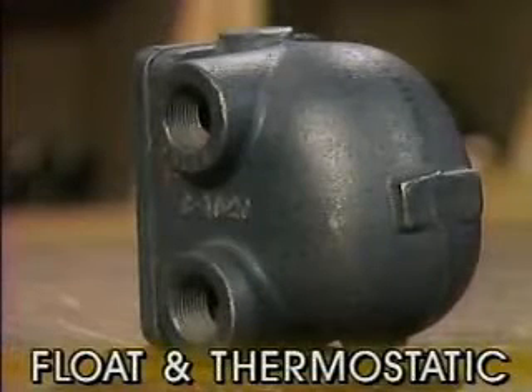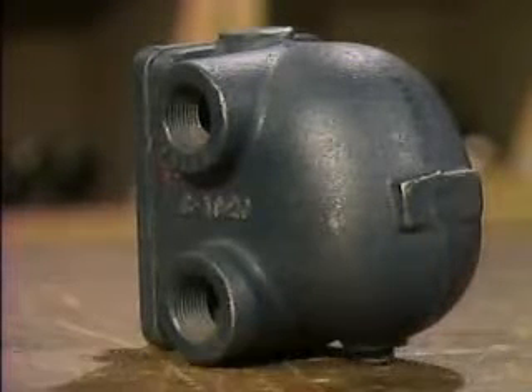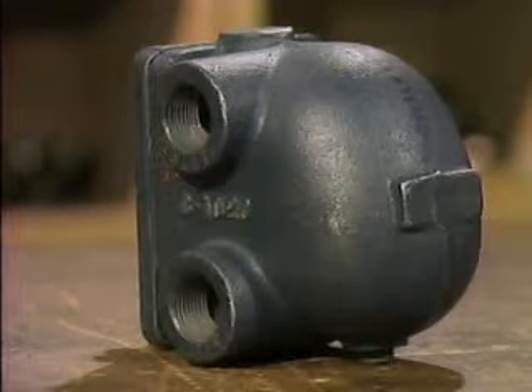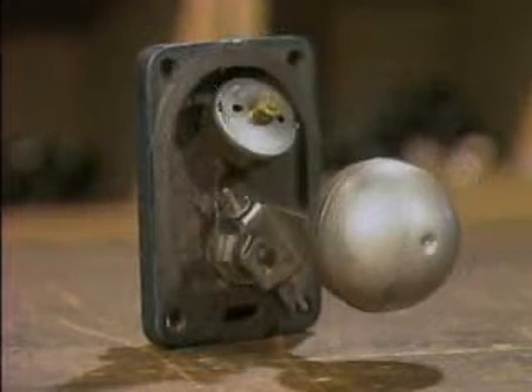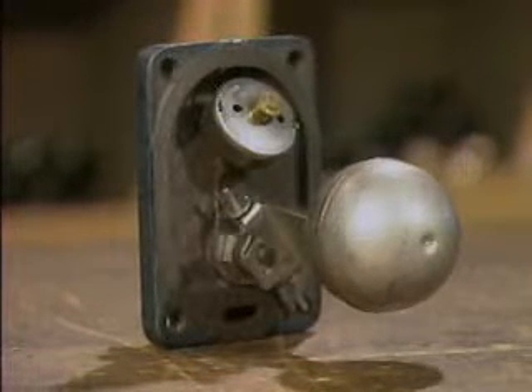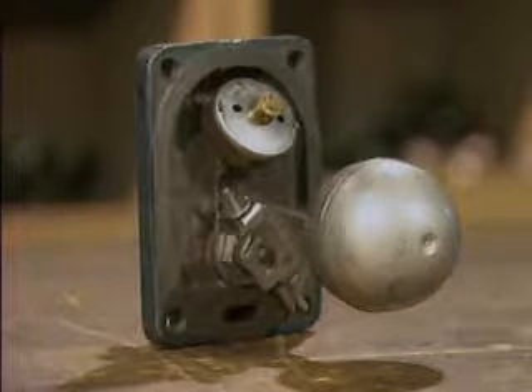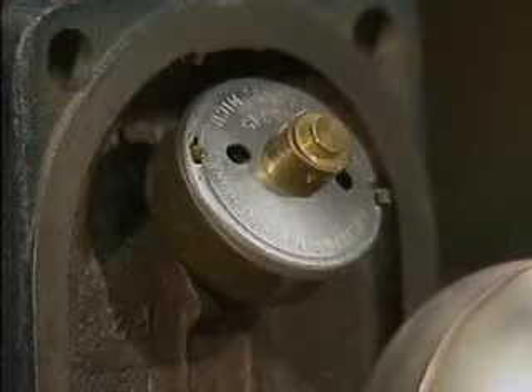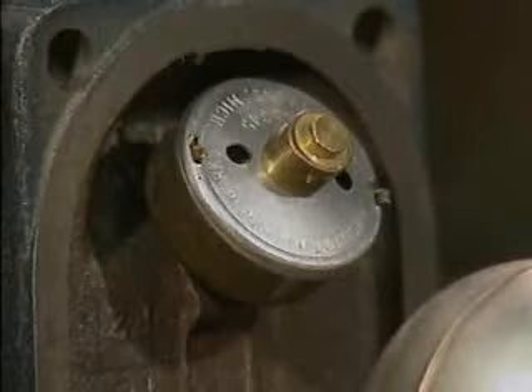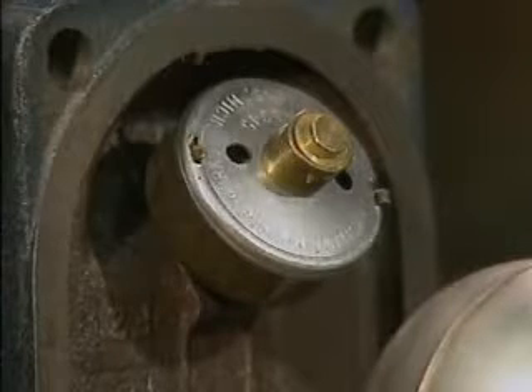This is a float and thermostatic, or F&T trap. It's generally classified as a mechanical trap because one of its major internal parts is a ball-type float mechanism for removing condensate. However, it also has a thermostatic bellows that reacts to changes in temperature and is used to remove air and non-condensable gases. So in this respect, the trap is thermostatic.